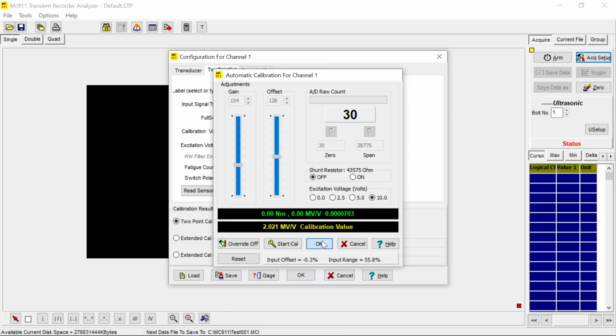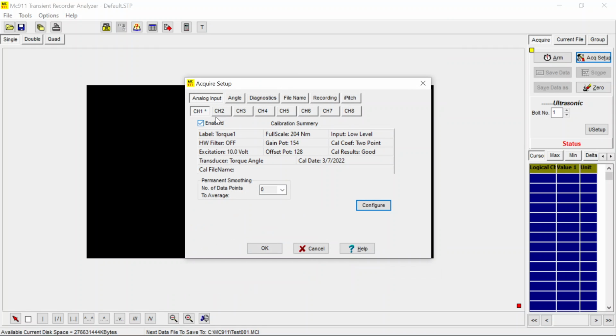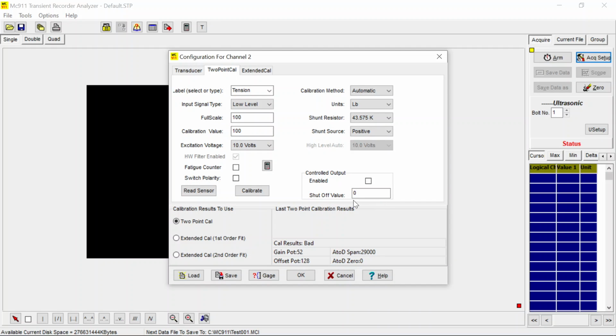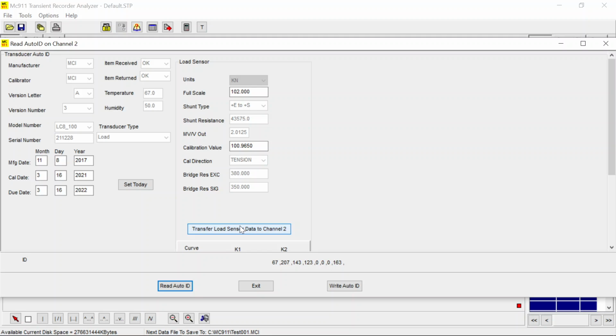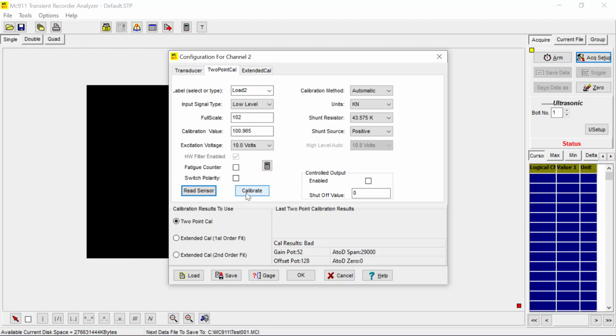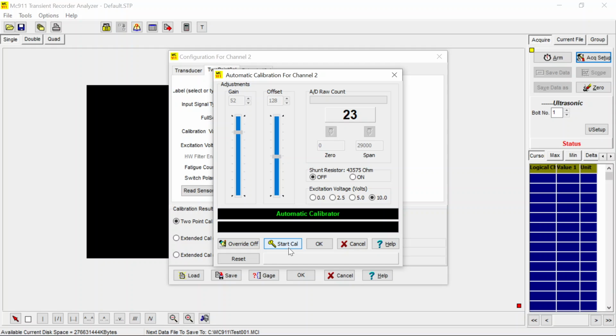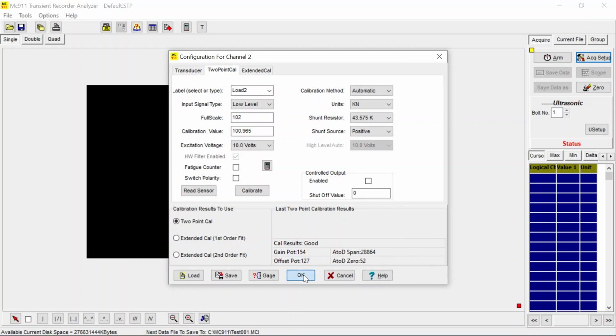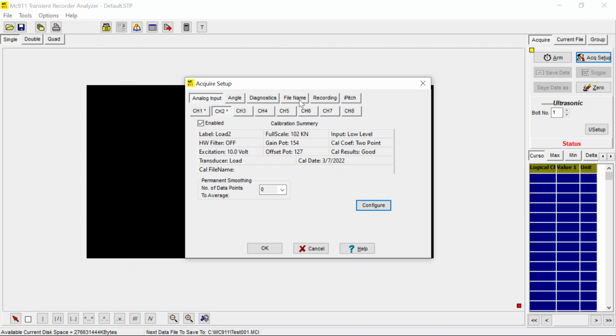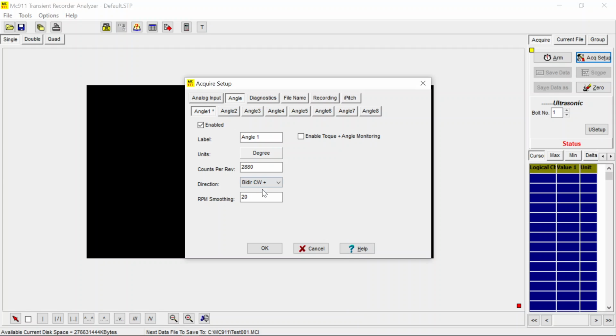It's done. And let's go into channel 2, which is our load cell. Enable this and configure. Again, we read the sensor, transfer the results. We have 100 kilonewton load cell in the device. Calibrate it. Make sure there is no load on the bolt. So we're done here. So back to here, we have to make sure the angle is correct, which is 2880 with our sensor. When you read the sensor, it automatically takes care of this number. You don't have to worry about it.